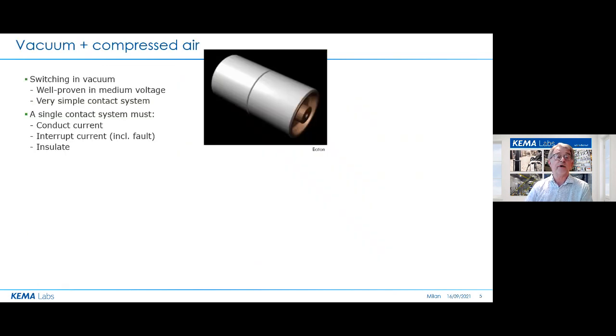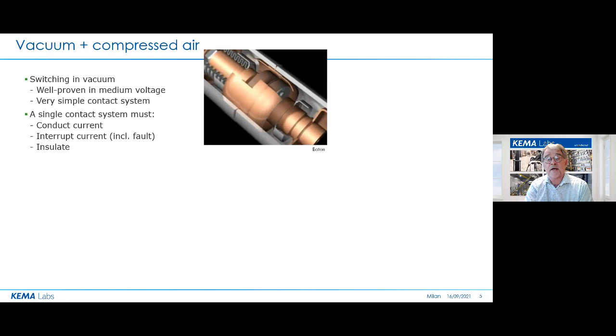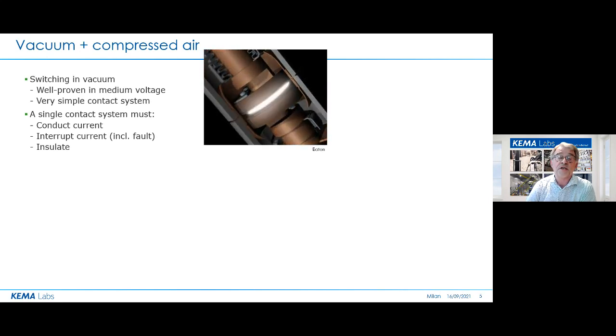The other type we will see now, it is the vacuum circuit breaker. Well, the vacuum breaker, we know, of course, already a long time because it's the workhorse of medium voltage. And one of the key points, one of the attractive sides of the vacuum breaker is that its contact system is very simple. Well, I will again show an animation on how a current interruption in such a vacuum interrupter looks like. So a single set of contacts is involved here, and this single contact set has to make sure that it's conducting current in the closed state. It has to interrupt the current, including fault currents to the highest level, and, of course, it has to insulate as well.